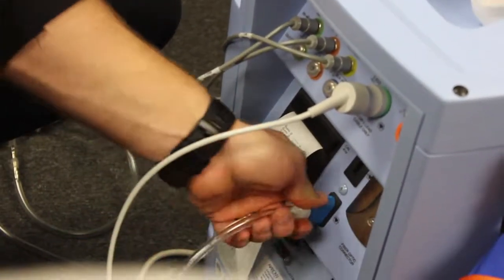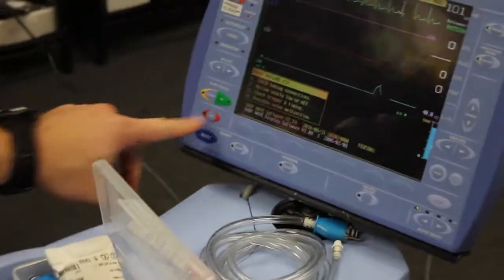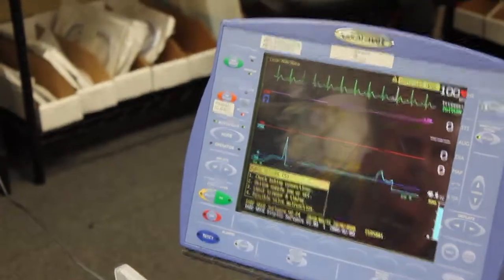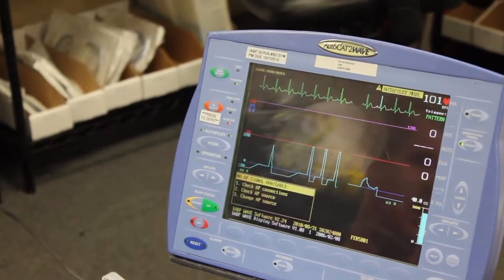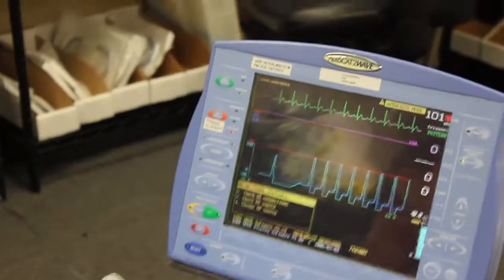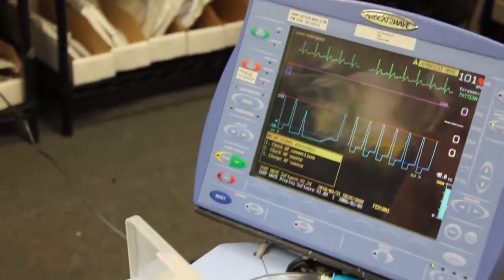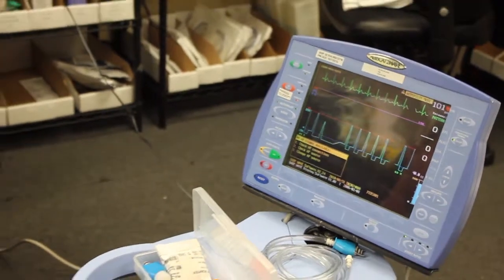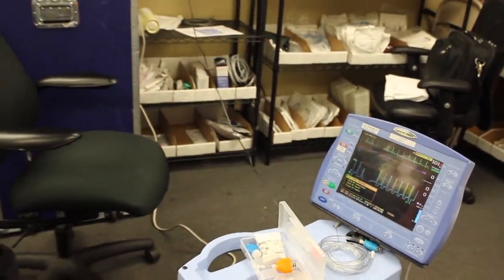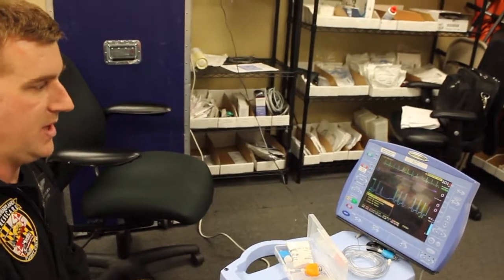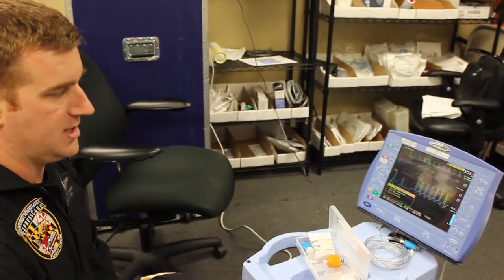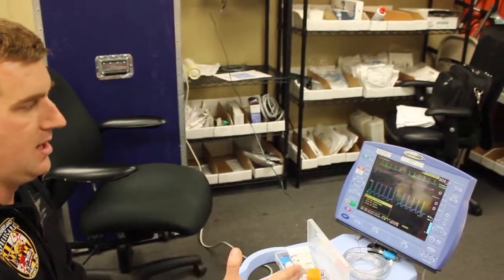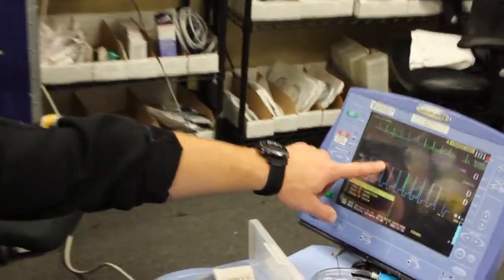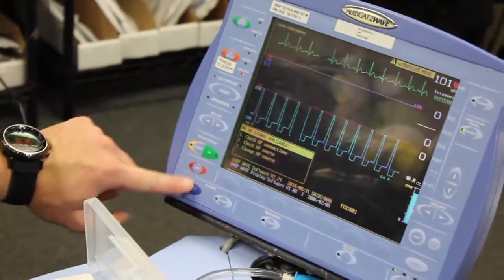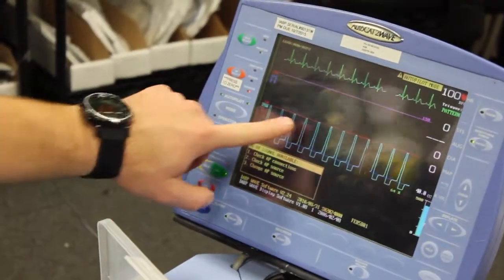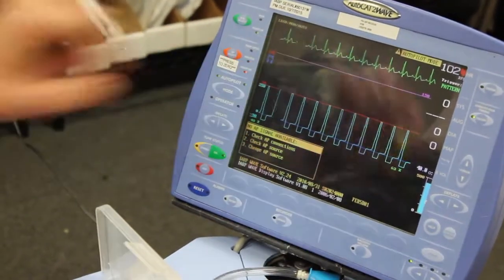Then I have to switch over to our trainer here, and then we're going to hit start, and we're going to start to pump. And we're pumping off the EKG source. So at this point, you're not going to have an AP source, because we haven't switched over the A line from the sending facility's balloon pump. But you let it get going and make sure that you're good, and you're getting good augmentation and good pumping off of it. You're not going to actually be able to look at your augmentation, but you should be able to look at the fact that your pumping is hitting. You can see where the peak of your balloon waveform hits pretty much right between your QRS complexes.